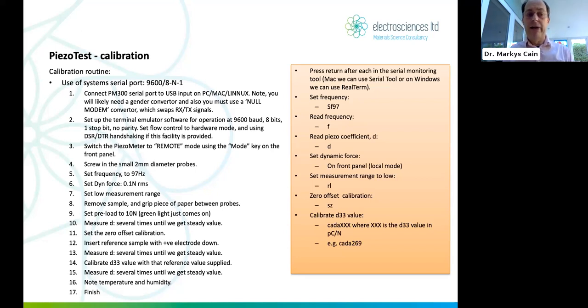So this is all about how you would calibrate the system, and the calibration routines for this system are certainly described briefly in the literature, in the user manual you get from Piezotest, okay? But it's not so obvious how you might do it. Number one, you need a serial port, okay? And in modern day computing, how many people have got a serial port on their laptops? Or how many people even use the concept of a serial port to do anything whatsoever? Well, if you use Arduinos and so on, of course you will, but a lot of people don't. So this is number one.